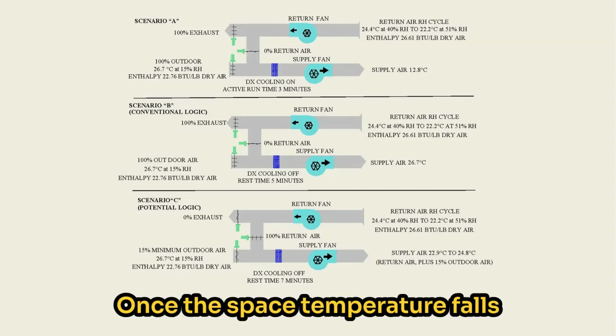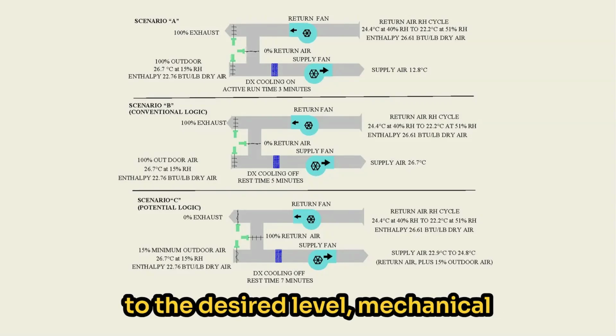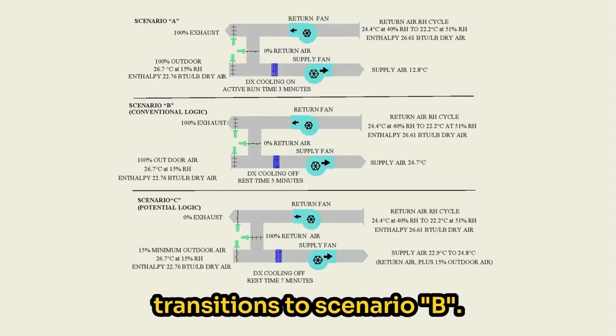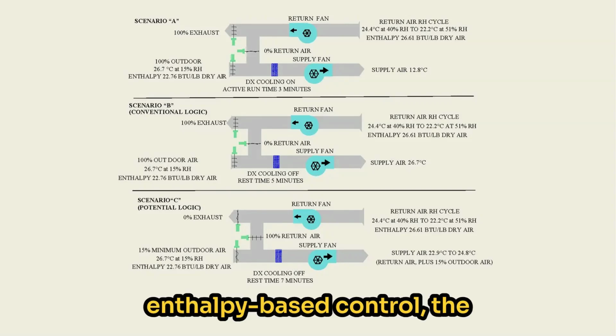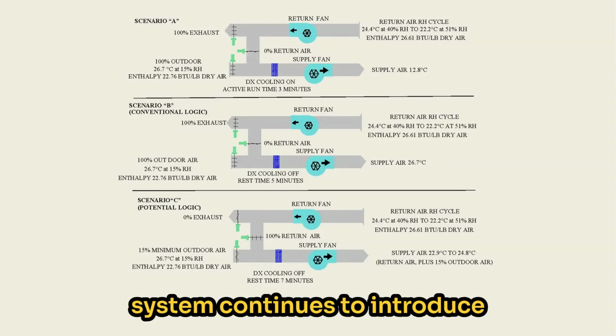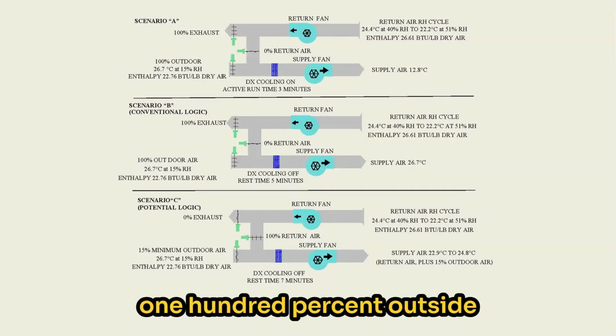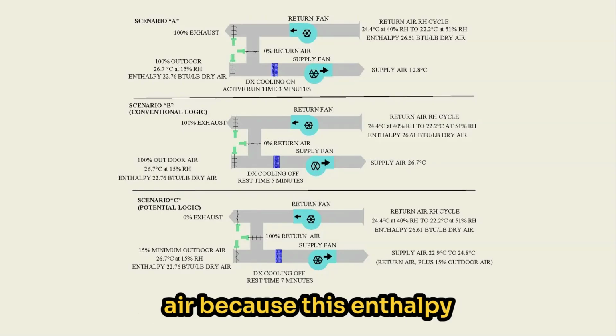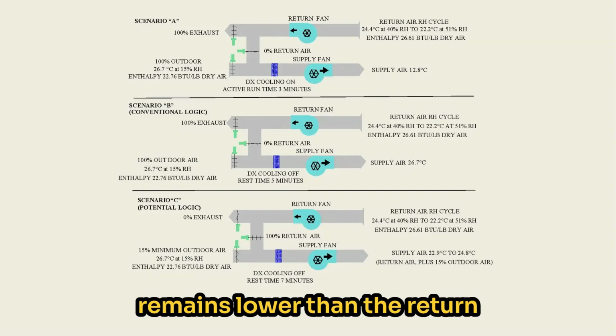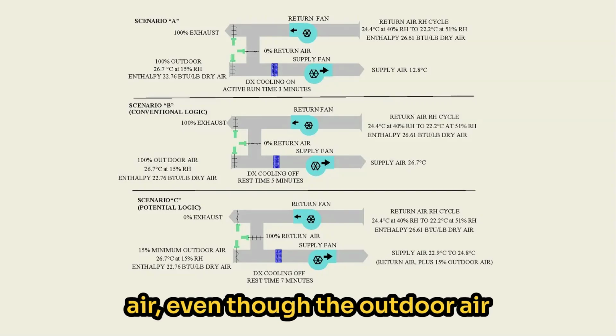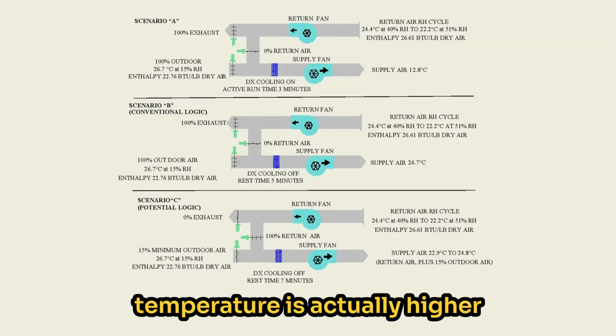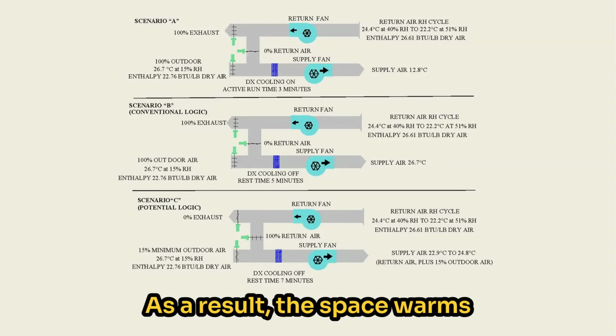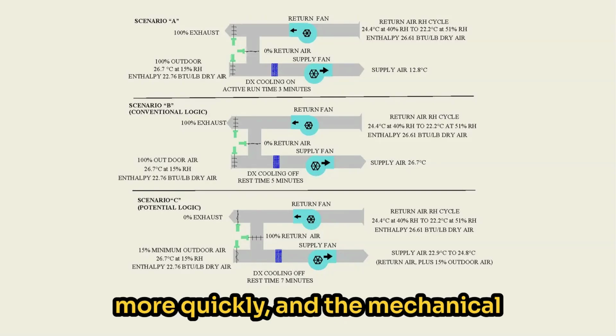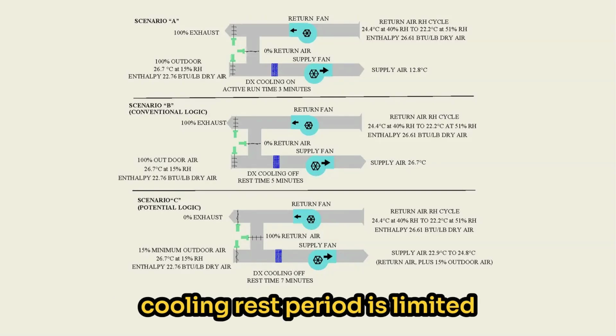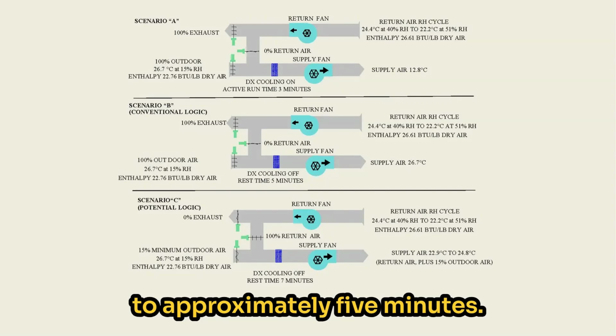Once the space temperature falls to the desired level, mechanical cooling shuts off and the system transitions to scenario B. Under conventional enthalpy-based control, the system continues to introduce 100% outside air because this enthalpy remains lower than the return air, even though the outdoor air temperature is actually higher than the return air temperature. As a result, the space warms more quickly and the mechanical cooling rest period is limited to approximately 5 minutes.